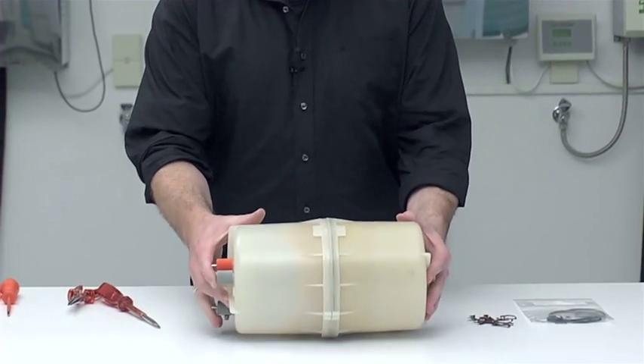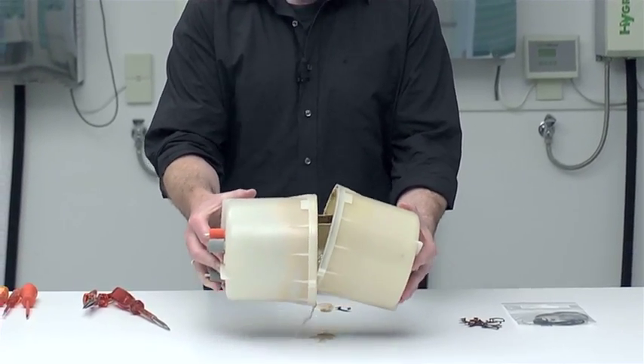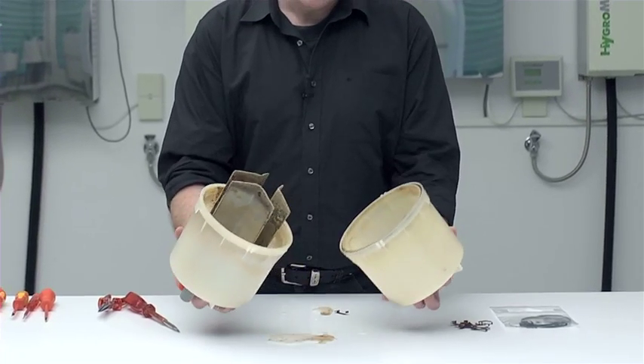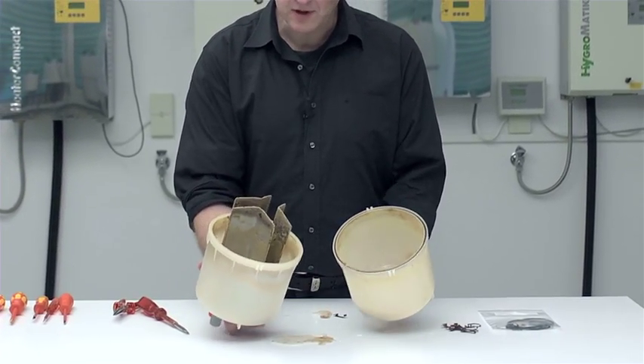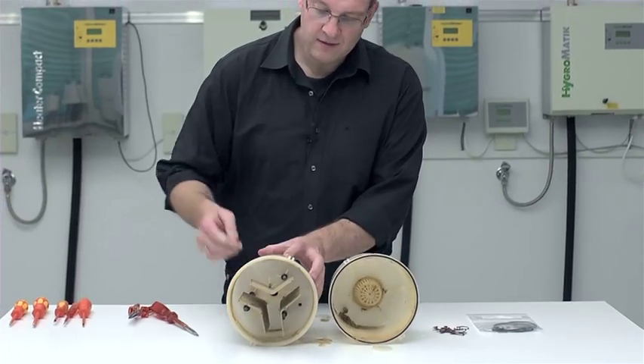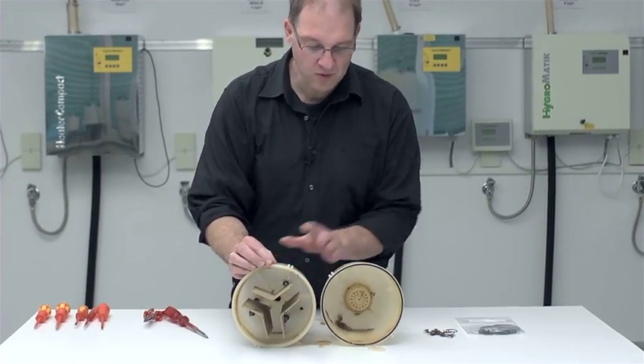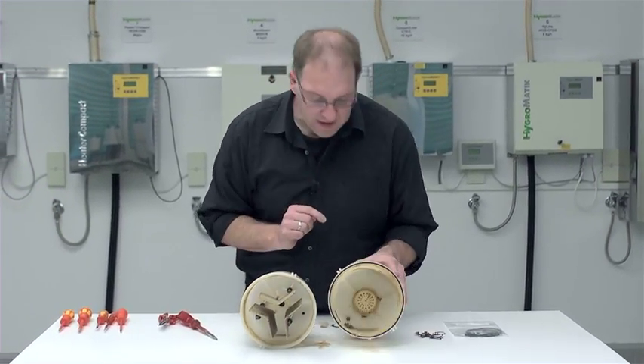Now I can open the cylinder in the middle. You can see a little water does still come out. Here we have some light mineral deposits on the electrodes and some deposits in the lower part.